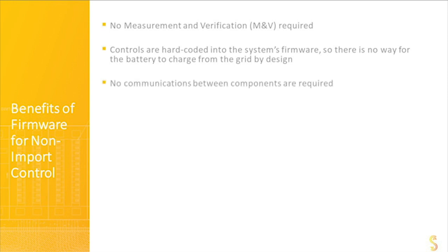This doesn't rely on communications whatsoever. Utilities and manufacturers, we worry about communications. What if communications drop? So if communications are vital to the health and safety or compliance of an operating system, then you better make sure those communications are really robust and you better test and verify and UL list all those communications. Well, not in this case. This is simply done with power control or voltage control, period.